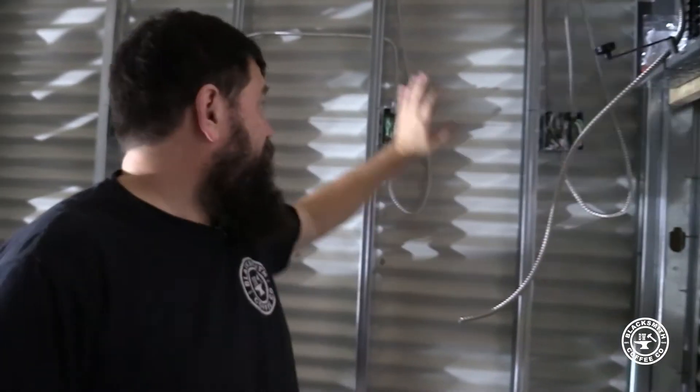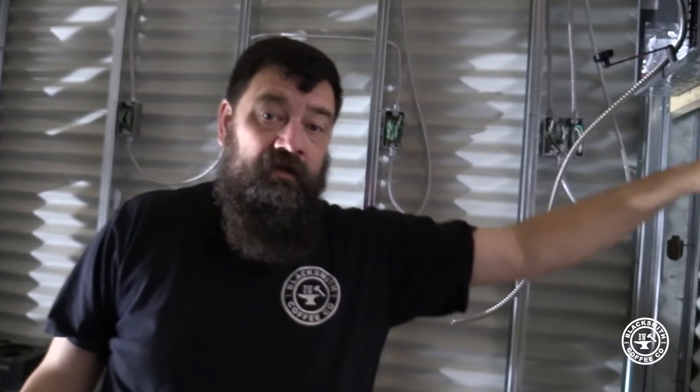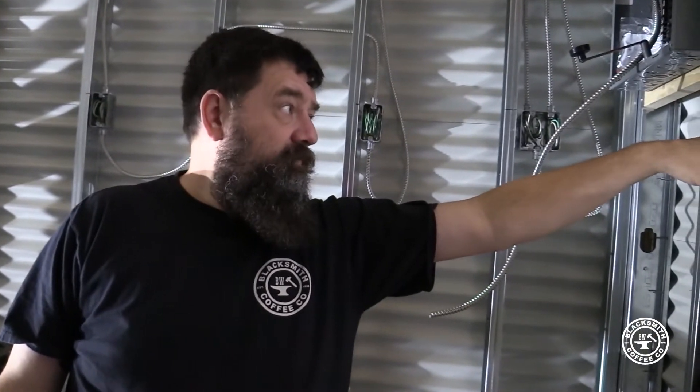They're all LED, so the draw is nothing. I'm running, as I told you, I was running 12-2 with ground for all of my outlets. For this, I'm running 15 amps, so this will be 14-2 with ground.